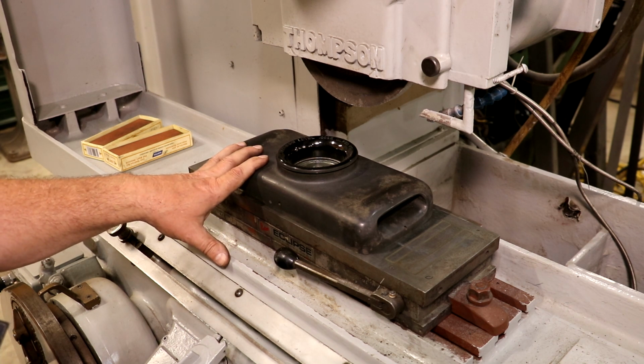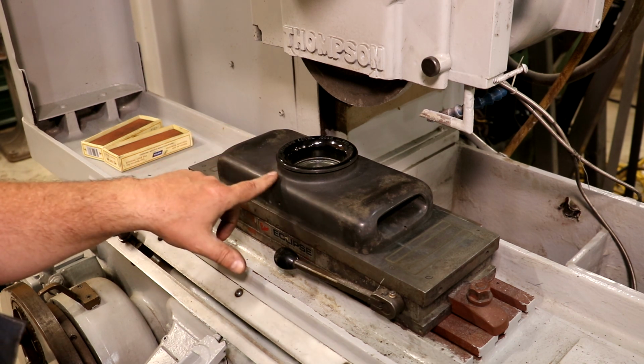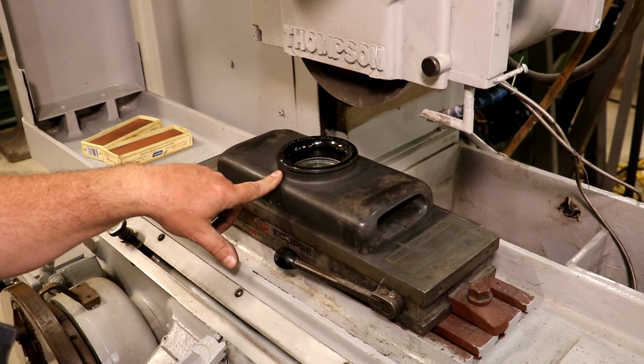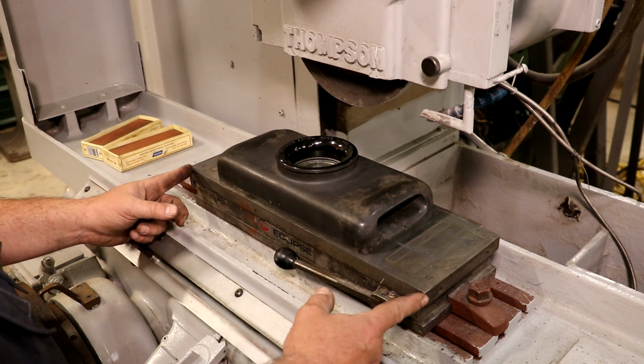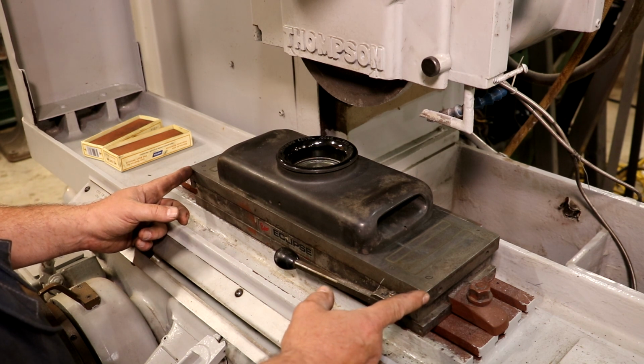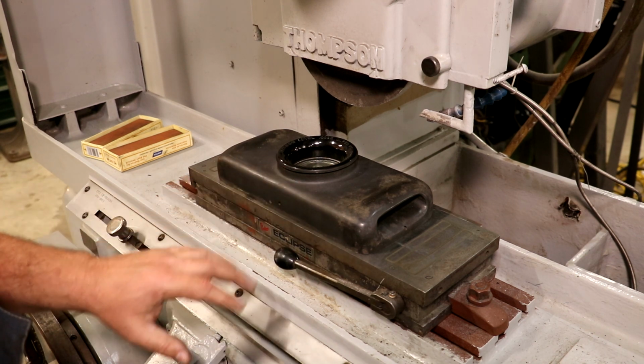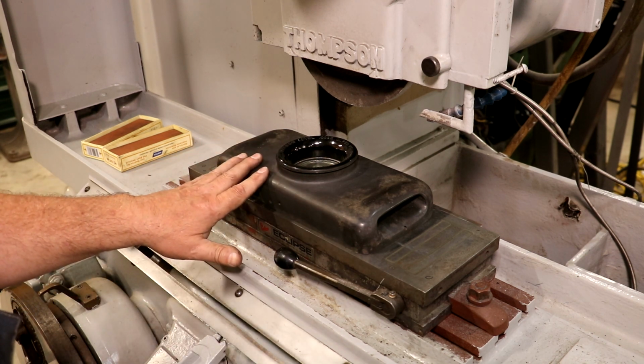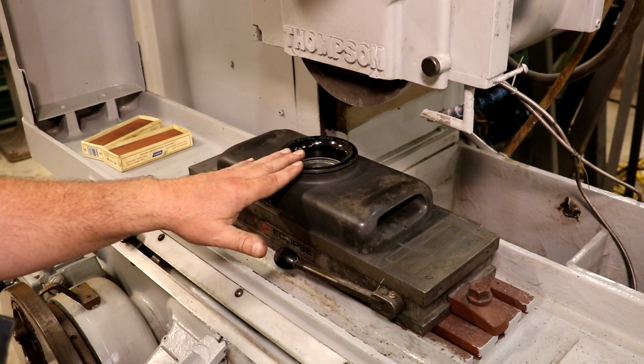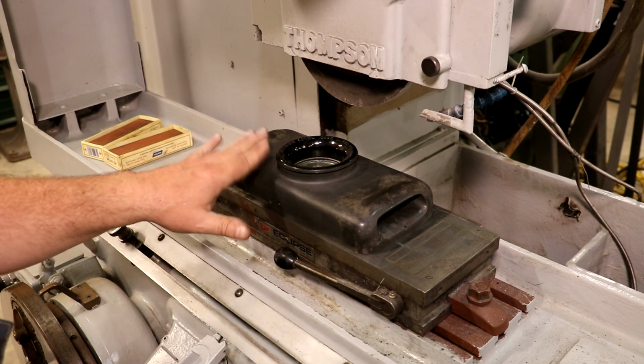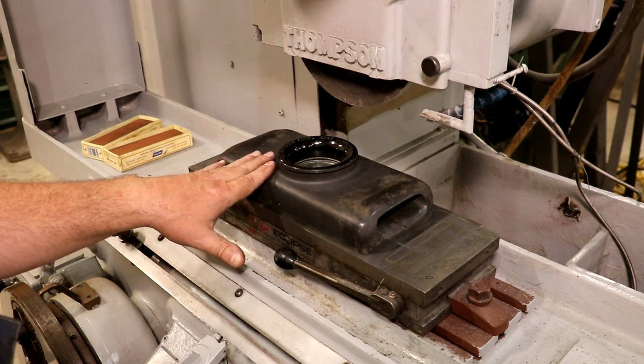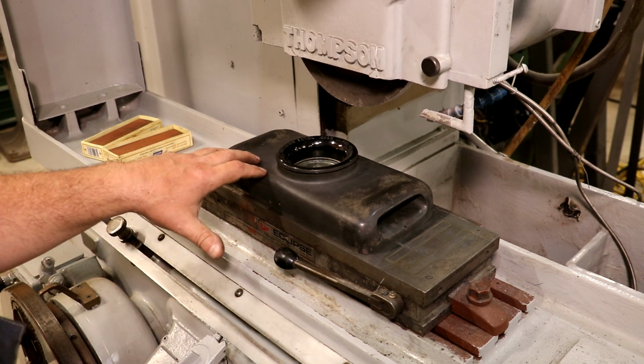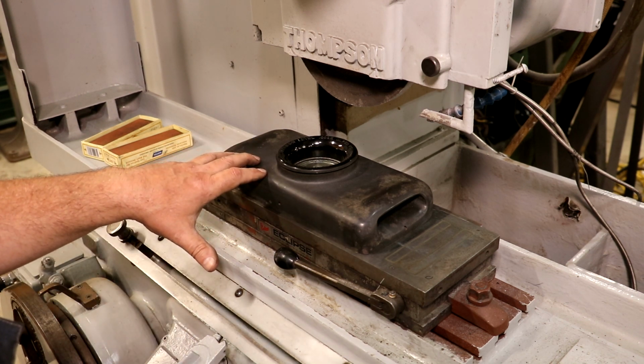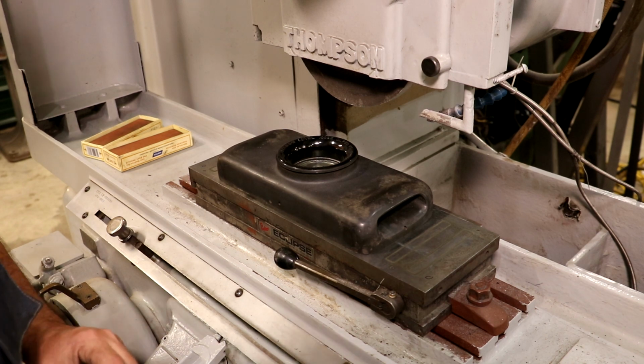Your typical Starrett machinist levels are accurate to 0.005 of an inch per foot, each line on that level. This one, the Starrett Master Precision level, the Starrett 199, is accurate to 0.0005 per foot. It's super touchy, but when you get it leveled up, it is dead nuts level. 0.0005 per foot is not very much at all.